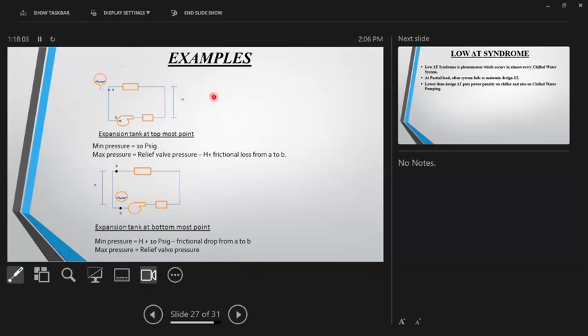P1 and P2, whenever we talk, are the pressures in the expansion tank. Now let us consider an example where your chillers and pumps are in the basement and your expansion tank is on the terrace. So this was the situation, and H was the height of the building or the hydraulic circuit. In this case, I need to find the minimum pressure and maximum pressure in the system. The minimum pressure in the system should be 10 psig above atmospheric.